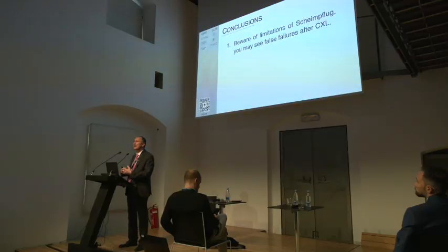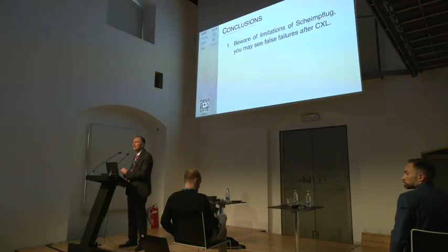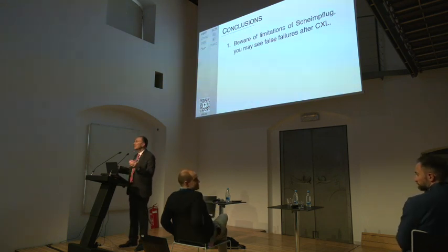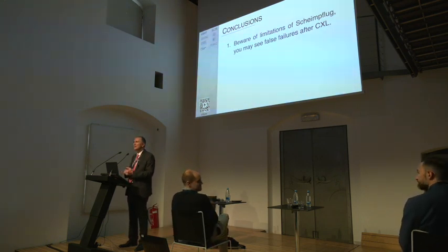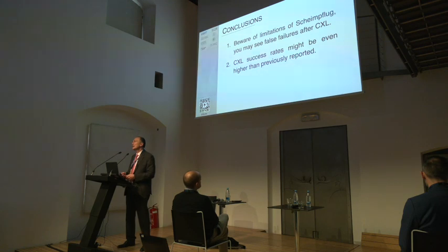So in conclusion, beware of limitations of Scheimpflug. I still use it every single day because it helps me a lot to monitor the healing. In a perfectly transparent cornea, Scheimpflug is awesome. It works very well, but as soon as you have haze or scar or anything that disturbs the light, just know what you are measuring.